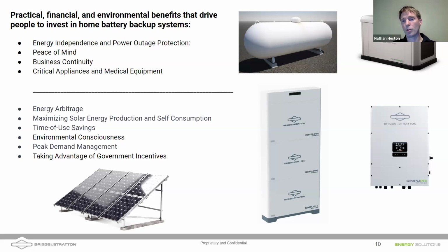Of course, in the off-grid world, you don't have the ability to pull power from the grid, and you might want to run a generator. Well, you can maximize the efficiency of your generator by pairing it with a battery system, so you reduce your runtime, etc. There's also the ability to integrate solar energy with an inverter system. And solar energy, you can think of solar panels like an energy pump. When the sun hits them, they pump that energy. If you have a battery system, you have the ability to store that energy and then use that at nighttime.